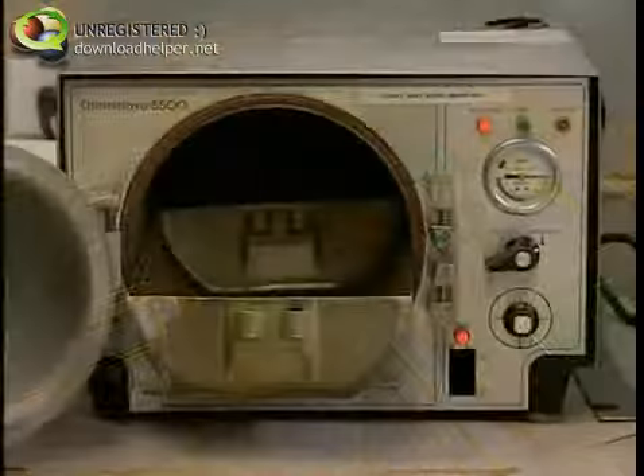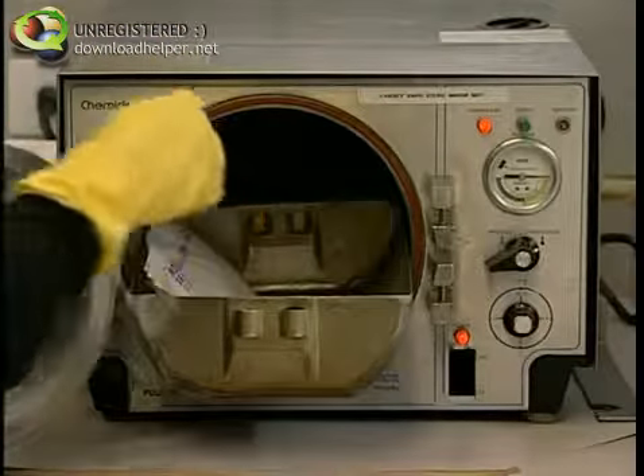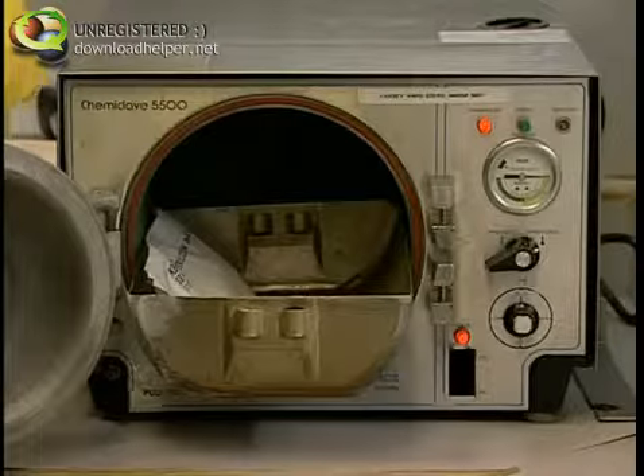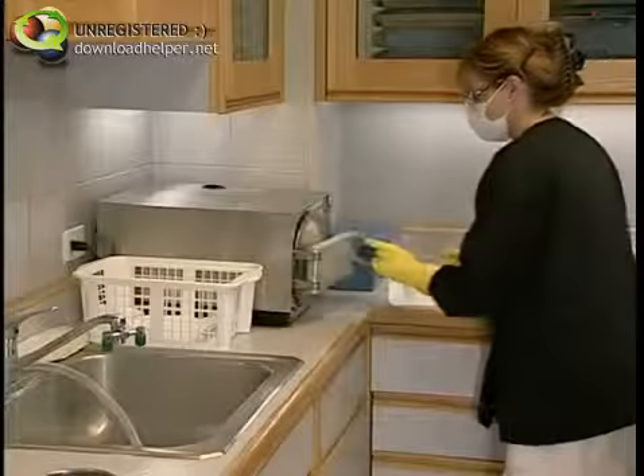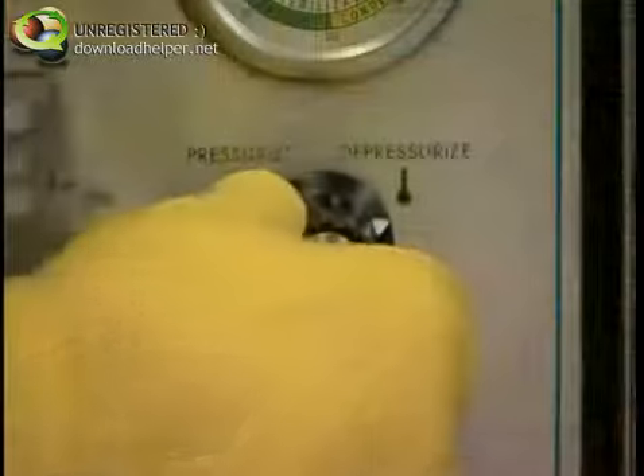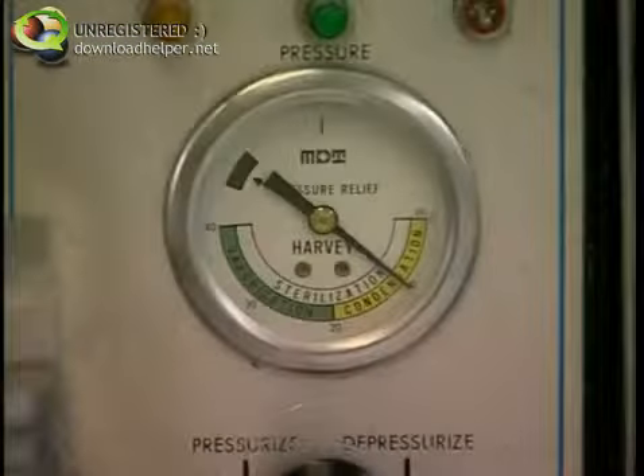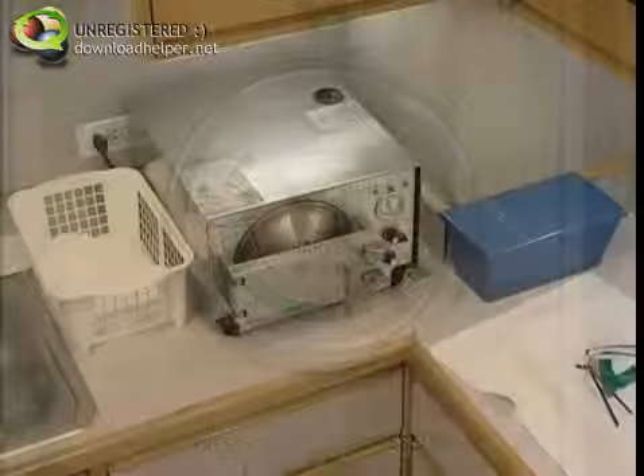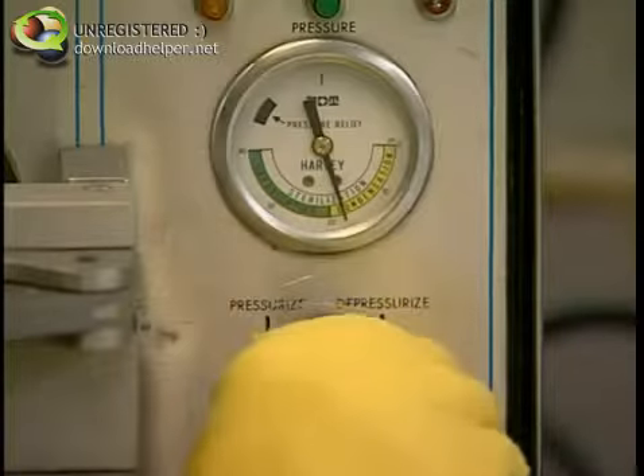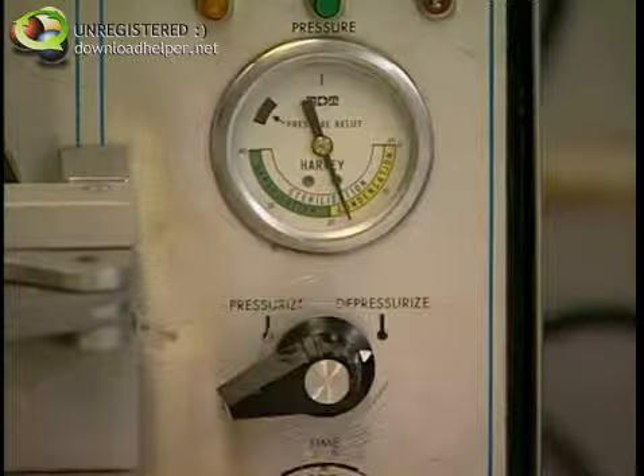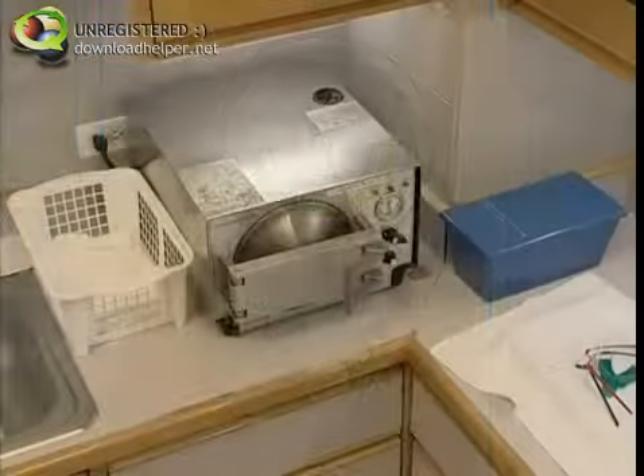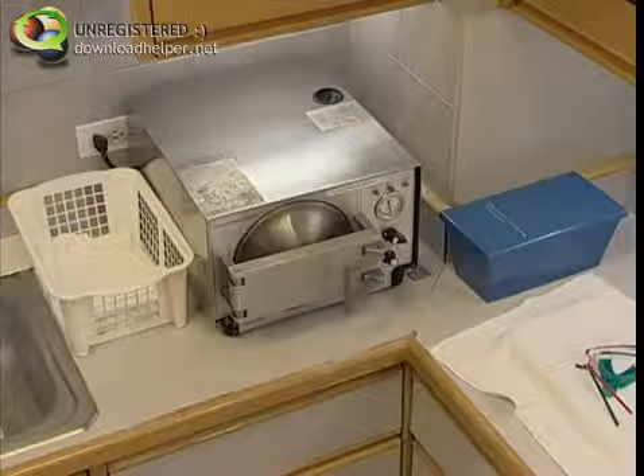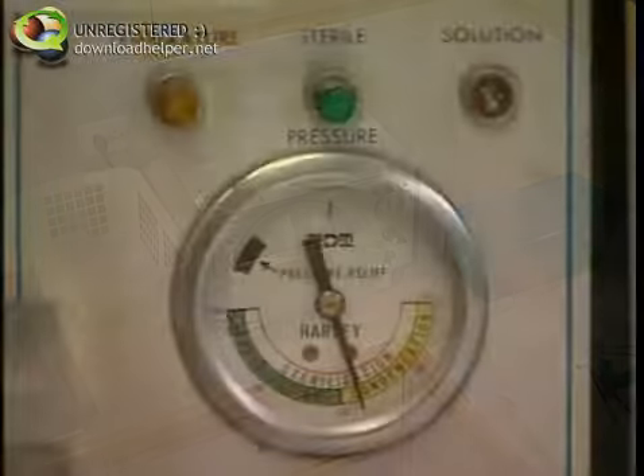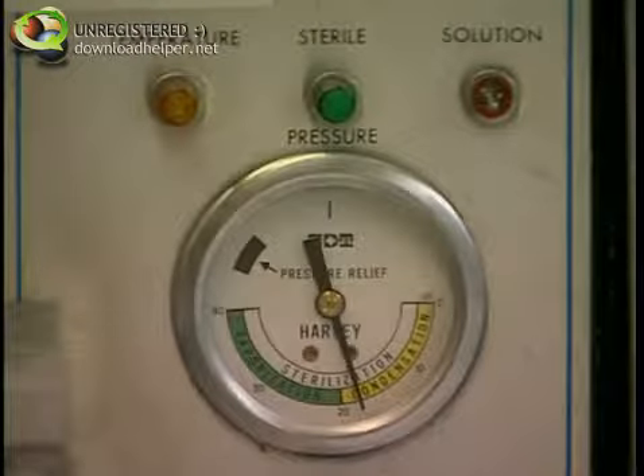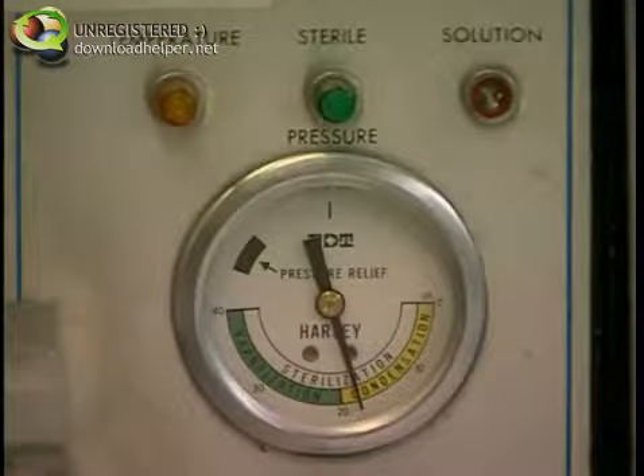The autoclave should not be overloaded in order to allow the steam to sufficiently kill all microbial forms. The temperature and pressure of the autoclave must reach the manufacturer's recommendation before the sterilization cycle can begin. Because of the pressure, an autoclave should never be opened until a safe internal temperature has been reached. If opened before the cycle has ended or before the unit has cooled, severe steam burns could occur. Check manufacturer's guidelines for a safe cooling temperature.